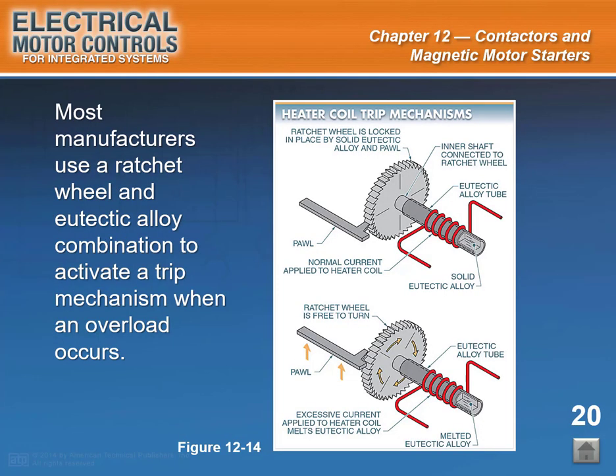Start of slide 20. Slide caption: most manufacturers use a ratchet wheel and eutectic solder alloy combination to activate a trip mechanism when an overload occurs. See Figure 12-14. The eutectic alloy tube consists of an outer tube and an inner shaft connected to a ratchet wheel. The ratchet wheel is held firmly in the tube by the solid eutectic alloy. The inner shaft and ratchet wheel are locked into position by a pawl locking mechanism, so that the wheel cannot turn when the alloy is cool and solid.